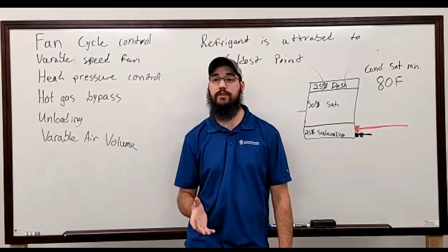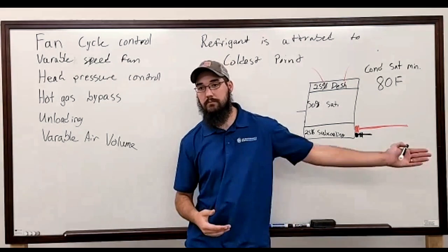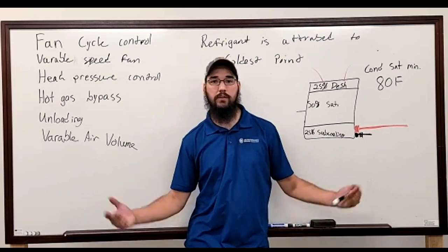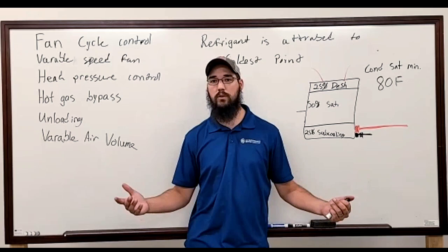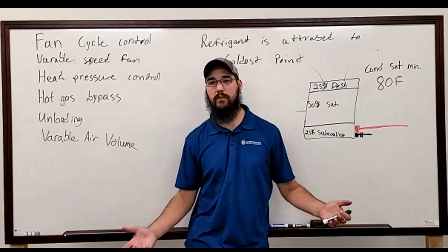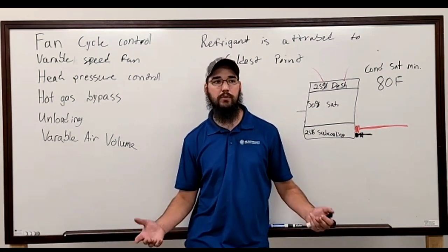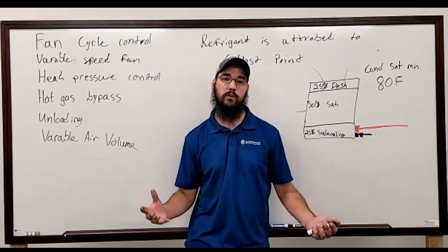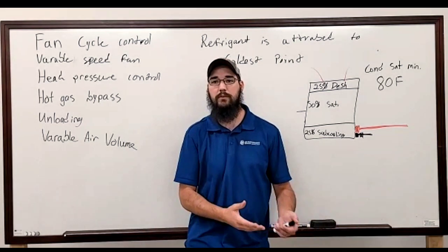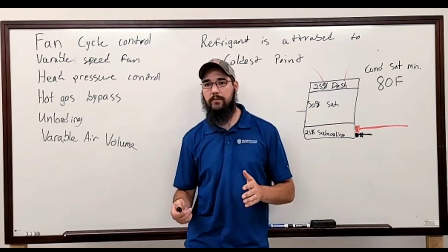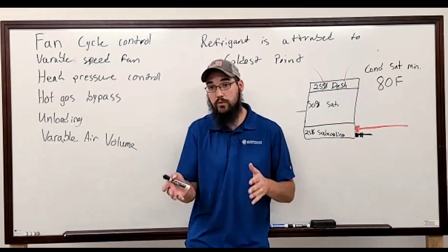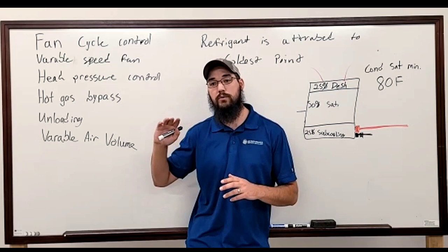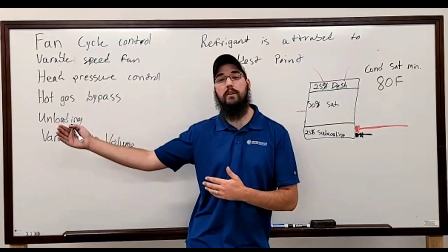Right, and that is traditional technology. Just like at one point in time, fixed orifice and capillary tubes were the way we controlled all system load and superheat, and then TXVs came out and that just rocked the AC world for decades. And we're really just now getting to the point where, well, in the last 20 years, that's become the new standard. And as soon as it did, EXVs hit the market, and EXVs are currently rattling everybody's world because they struggle to understand them so much. They're just a simple stepper, really not that complicated. In the same way, 60 hertz was an old standard and is still used today, but another 10, 20 years from now, you can throw that 60 hertz value to the wind because it's going to be the old school way of things.